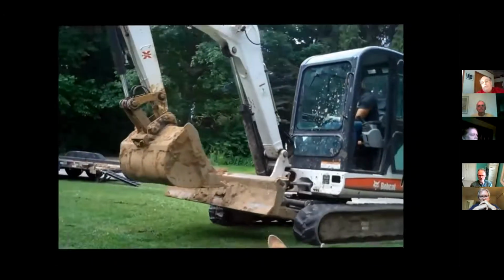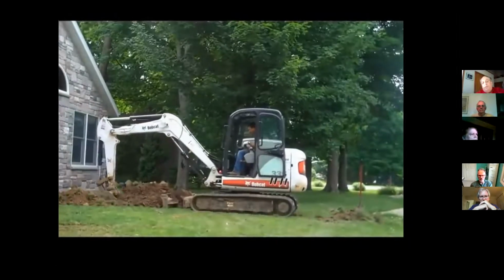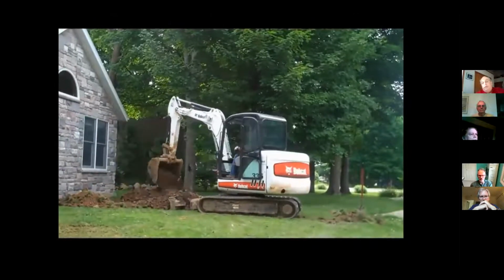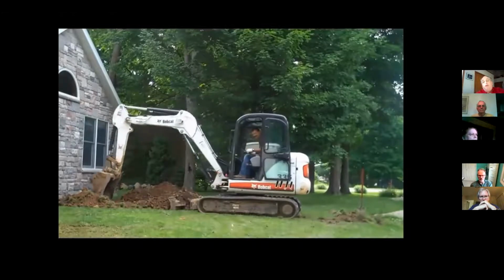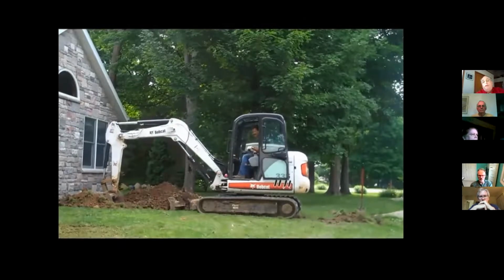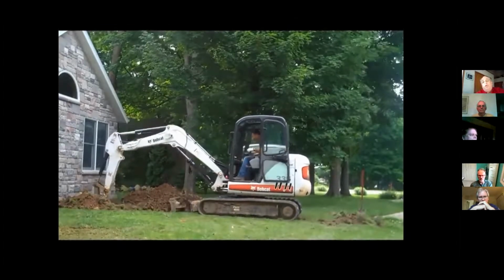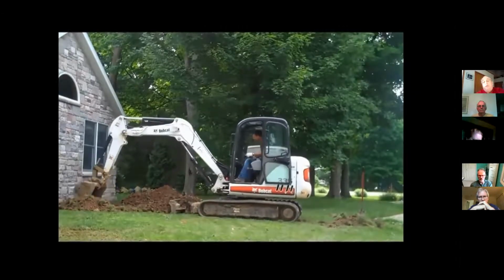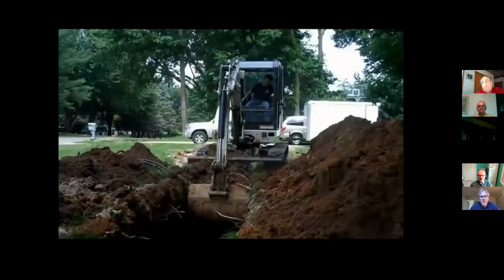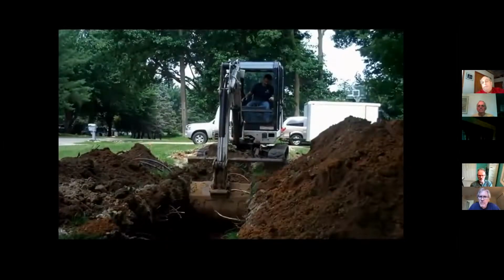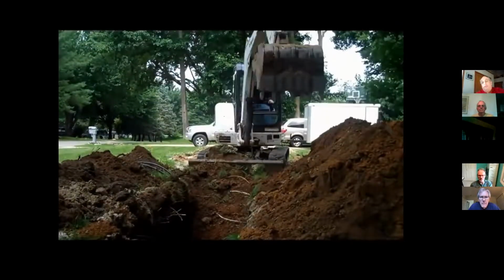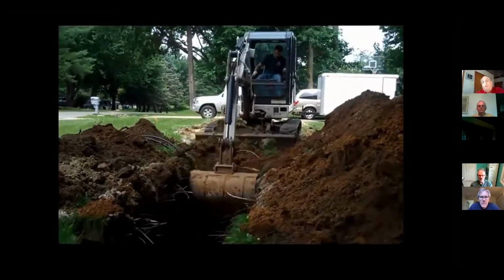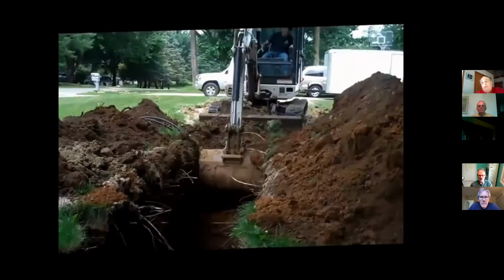Then the loop contractor trenches about 4 to 5 feet down and connects the 5 vertical loops, which used 3/4 inch plastic tubing. He now uses 1.25 inch plastic tubing to connect the circuits and bring the medium into the house.